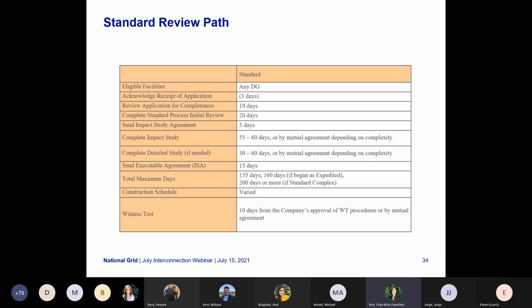And if a detailed study is applicable and necessary, then it would be 30 to 60 days or by mutual agreement, depending on the complexity. The ISA would then be delivered 15 days afterwards. And then essentially the total maximum days can be 135 days, 160 days, 200 days or more, depending on where it started, as well as the complexity of the project. The construction schedule will vary depending on what needs to get done for the project. And then the witness test will be from 10 days after the company provides approval of the customer-provided witness test procedure documents, or by mutual agreement if necessary. Next slide.